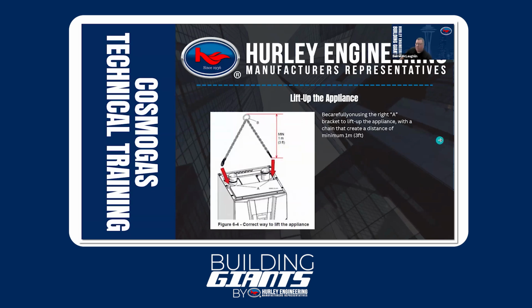Last, before we start getting into some more of the technical sizing things, just a common thing that's been seen is lifting and installation. So when you go to lift these, they've asked that you keep at least a 3-foot minimum between the lifting lugs and your lift point. That's just to keep the forces pulling upwards on the unit, because they can handle that well. But if that dimension is too tight, then it tends to pull the lifting lugs inward, and it can warp and distort the frame of the equipment.